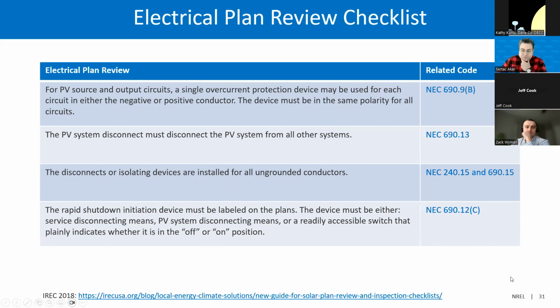One other thing is for the rapid shutdown. The rapid shutdown initiation device must be labeled on the plans, and the device must be either a service disconnecting means, PV system disconnecting means, or a readily accessible switch that plainly indicates whether it is in the off or on position.